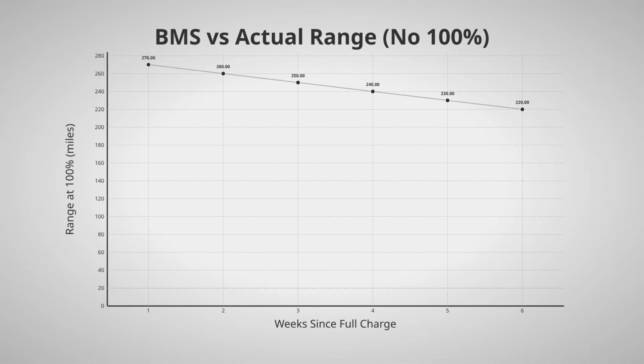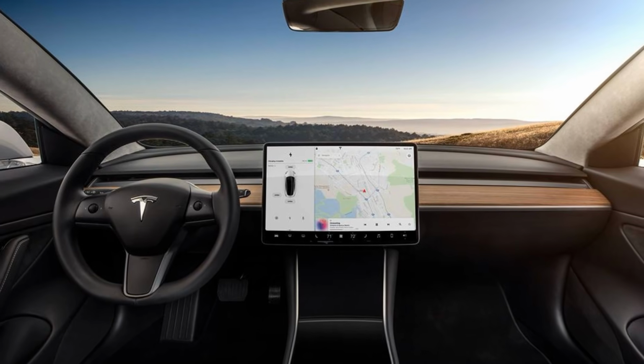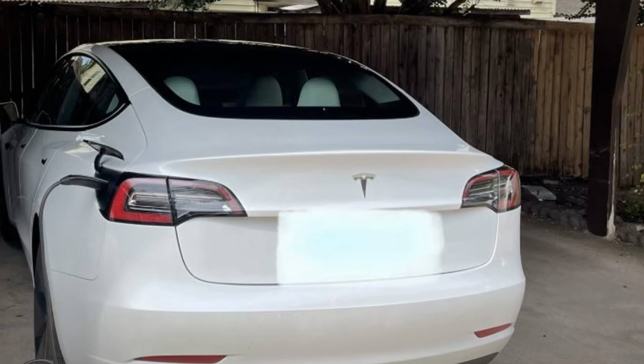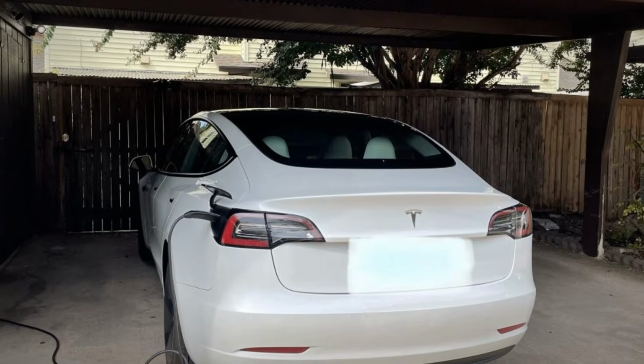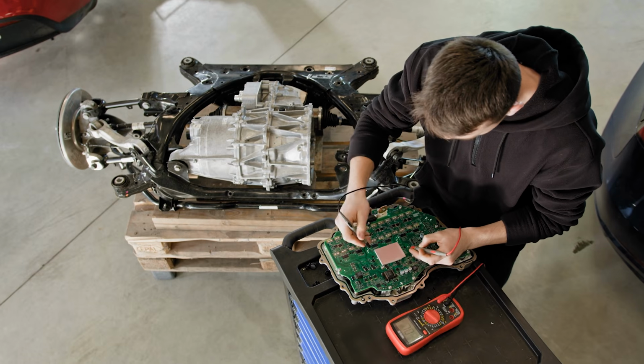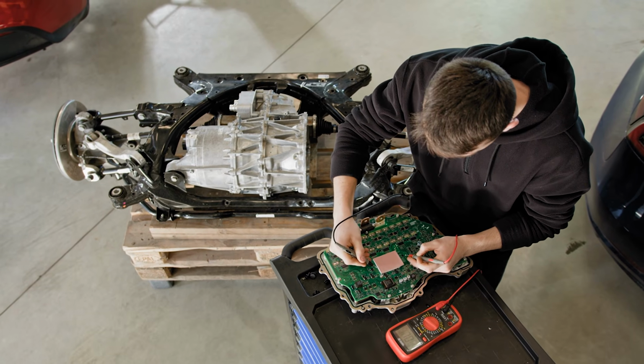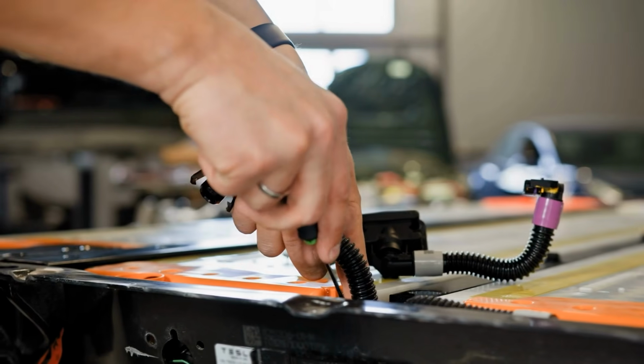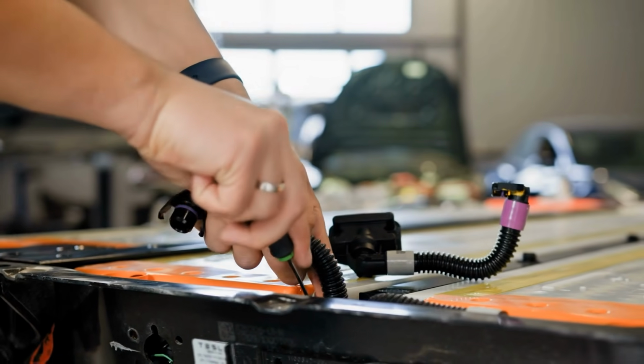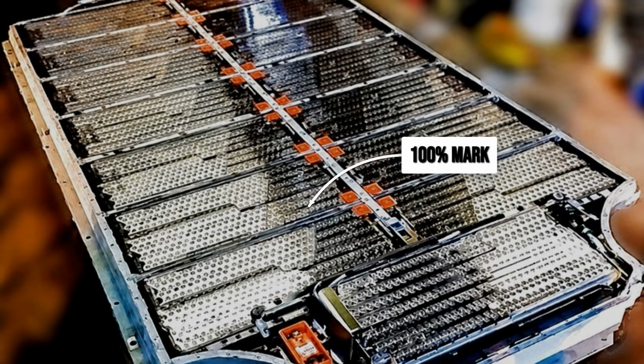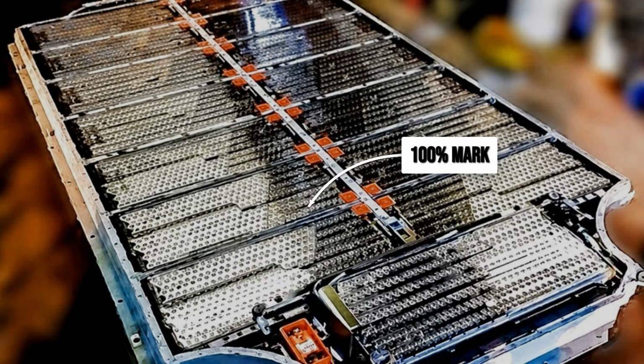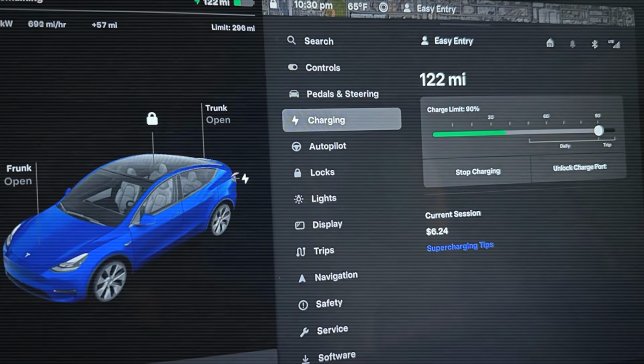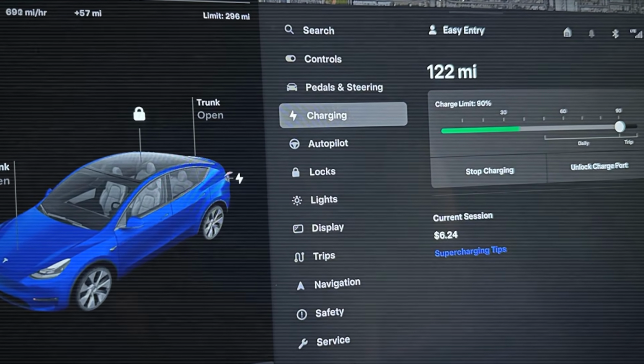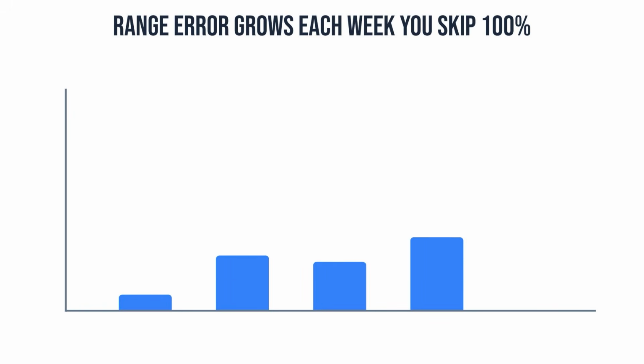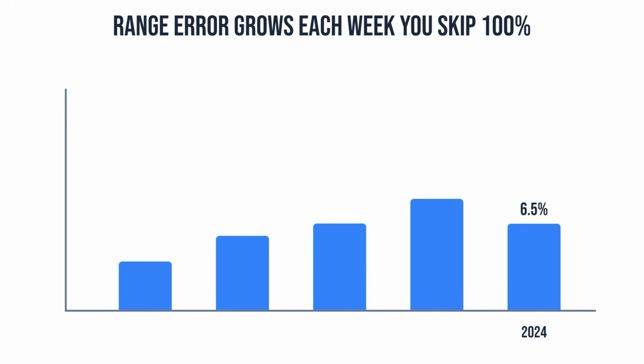Here is what actually happens when an LFP owner skips the weekly full charge for weeks or months at a time. The battery management system starts working with an increasingly inaccurate picture of the pack's real capacity. It knows roughly how much energy went in and roughly how much came out. But without the calibration anchor that a full charge provides, the accumulated error in its tracking grows over time.